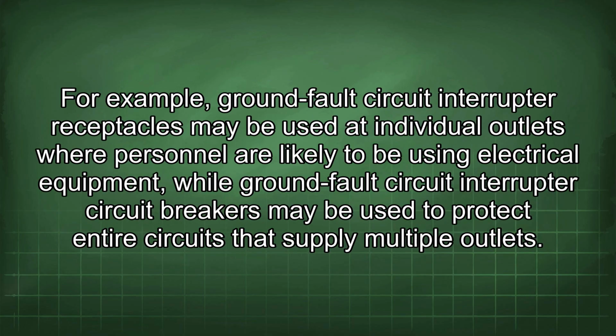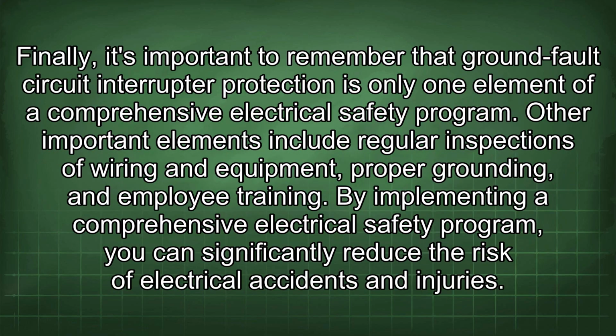For example, ground fault circuit interrupter receptacles may be used at individual outlets where personnel are likely to be using electrical equipment, while ground fault circuit interrupter circuit breakers may be used to protect entire circuits that supply multiple outlets. Finally, it's important to remember that ground fault circuit interrupter protection is only one element of a comprehensive electrical safety program. Other important elements include regular inspections of wiring and equipment, proper grounding, and employee training. By implementing a comprehensive electrical safety program, you can significantly reduce the risk of electrical accidents and injuries.